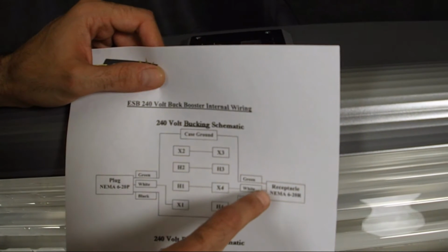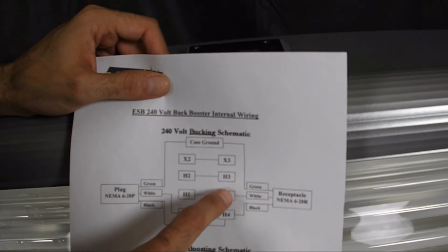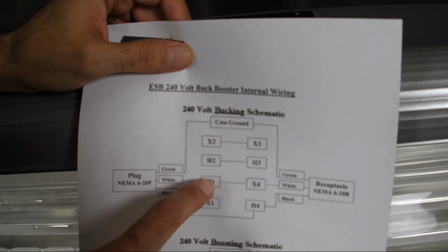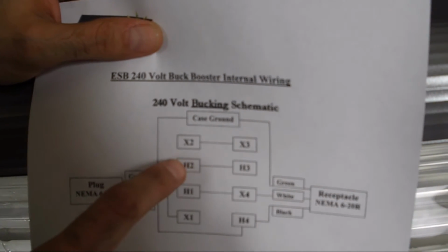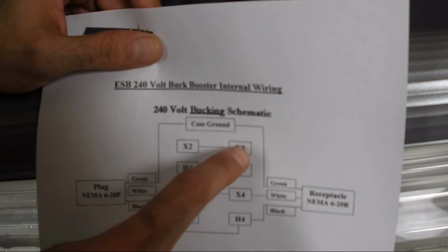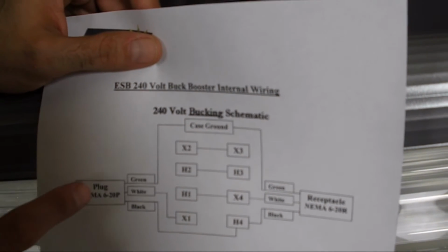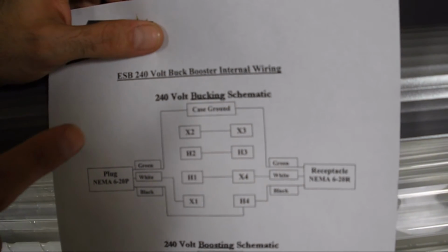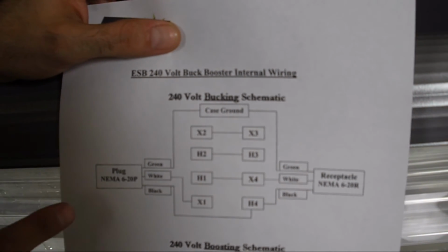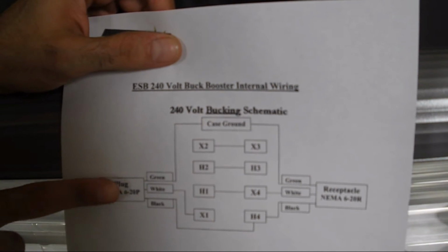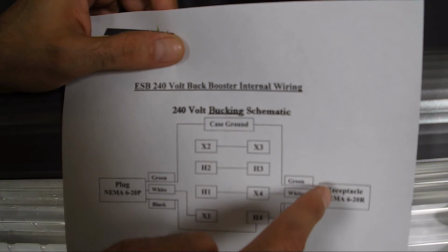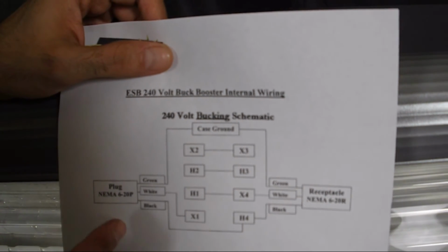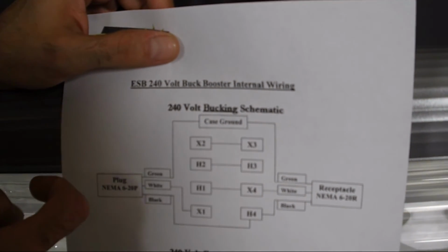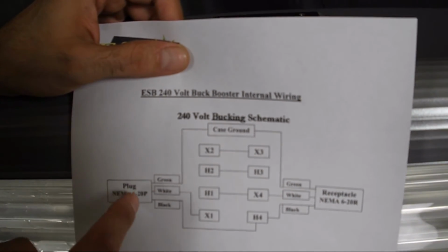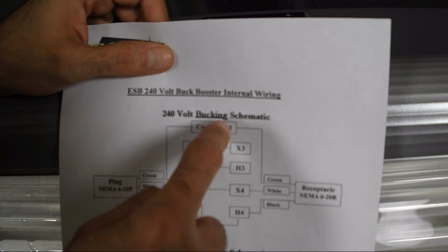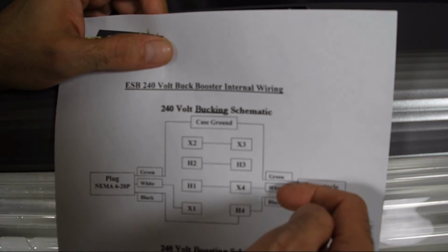From your receptacle, the white wire is going to connect to the X4 and H1. The H3 and the H2 will be connected together, and the X3 and X2 will be connected together. And this will provide you with the bucking configuration for your transformer. Whatever you have here is going to be dropped 17 volts coming out there.